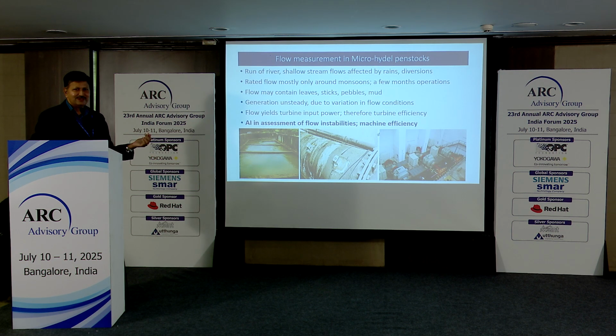That was one study we did, and it was not completed at this point of time, but this is one area where AI really is helping us because of the many varying conditions. We even went to site with a lot of insertion type flow meters to assess whether the flow meter there is working correctly or not. Of course, at this particular site there is no flow, so we tried to gauge the efficiency by other means. Basically we look at the electrical power output. The machine efficiency is determined as the ratio of output power to input power. Input power is determined from the discharge and the head. And IEC 41 is the standard against which we conduct all these tests.